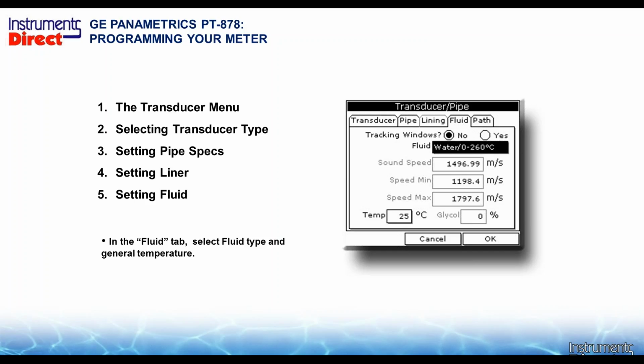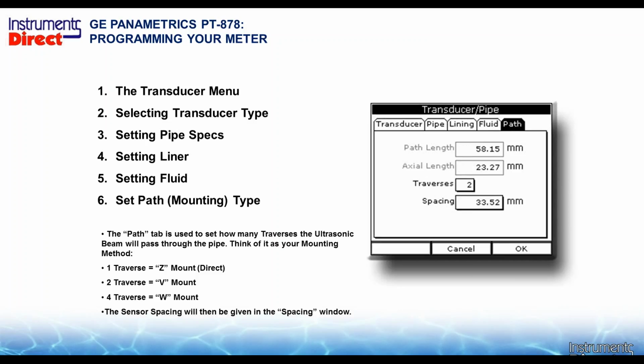So under most applications, probably 90% of your applications, you're going to be on water. Generically speaking, if the sound speed is plus or minus 10%, there's really minimal to nil effect on the performance of the device. So for example, if you had a water and glycol application, you can go to the other function and you can break out the percentage of glycol right there. I got 30% glycol, and I get this kind of temperature there. And when you go through the whole math thing, if you had 30% glycol and water, you're going to find out that you're usually far less than 10% differential sound speed from just on water. So you feel free to primp away, not that much different. If I had 75% glycol and water, that would be greater than the 10%. So most applications, mostly water, if you have that choice. If you pick something too far off the picture there, you may get no reading at all.